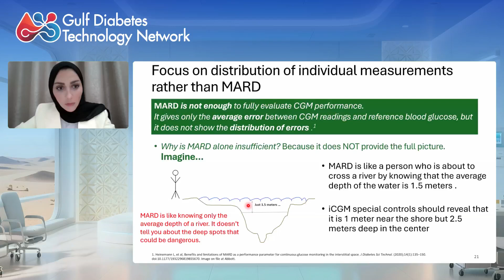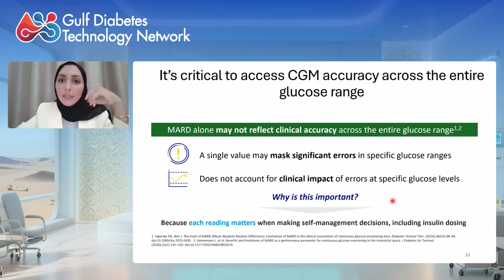So in CGM, it means that a device could have a good average error but still give us unsafe readings at low and high glucose levels. That's why CGM demands full testing to ensure safety across all situations and the average glucose. So MARD alone might not reflect clinical accuracy across the whole glucose range. And yes, it's important: all readings that the patients see on the meter are important, because each reading matters when the patient wants to make a self-management decision, specifically including insulin doses. So MARD is a single value that might mask significant errors in specific glucose ranges, and it does not account for the clinical impact of errors. So from now on, we should start looking beyond the MARD to evaluate the accuracy of a CGM.